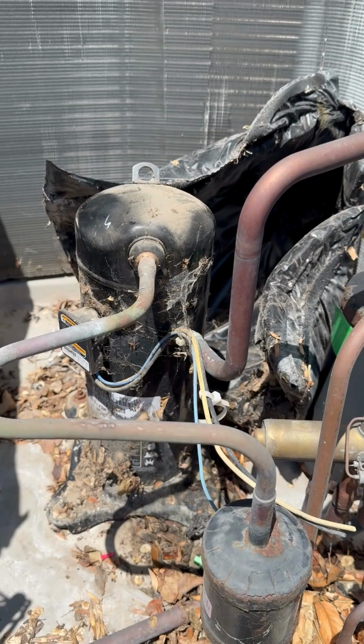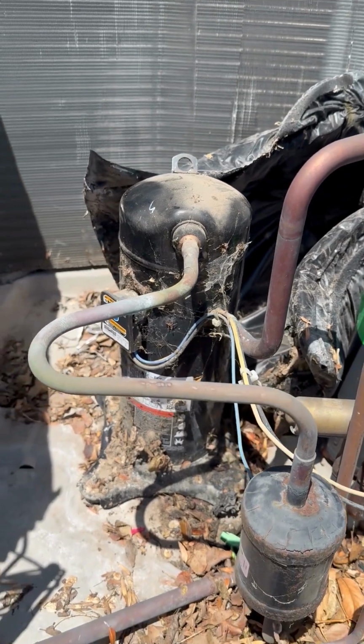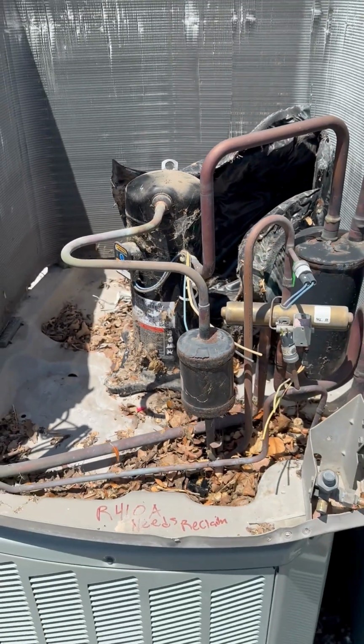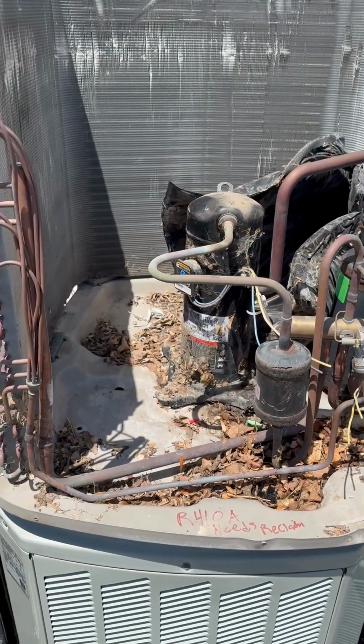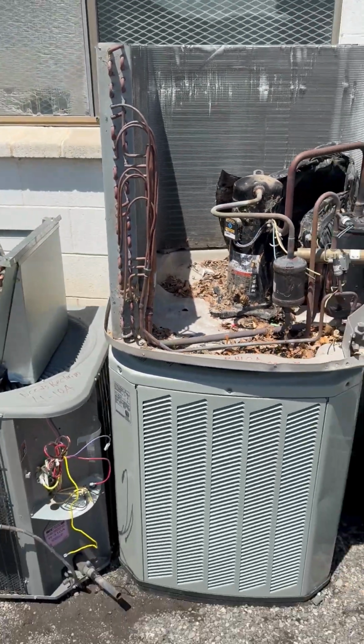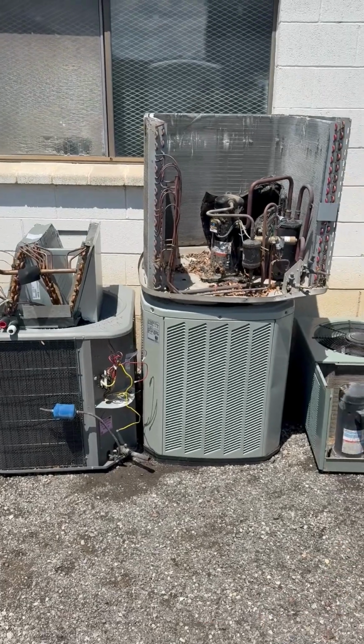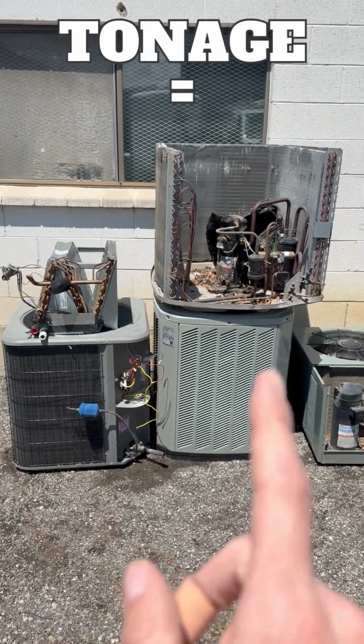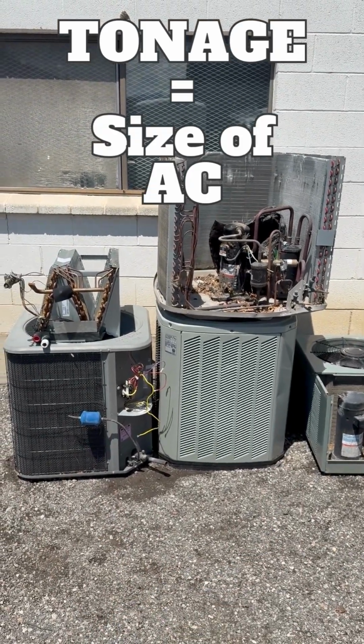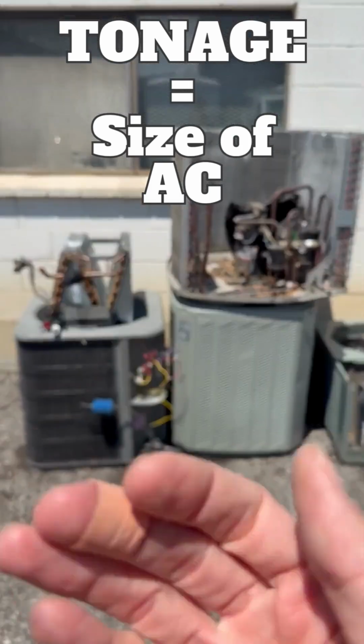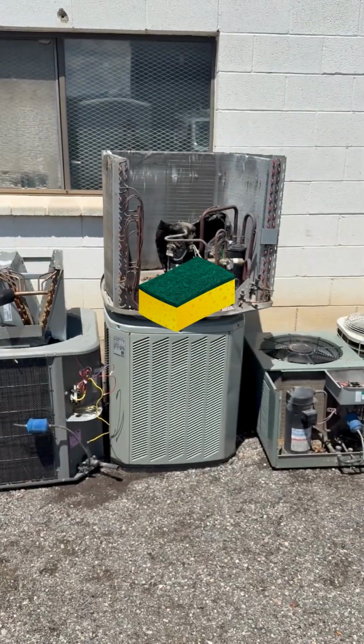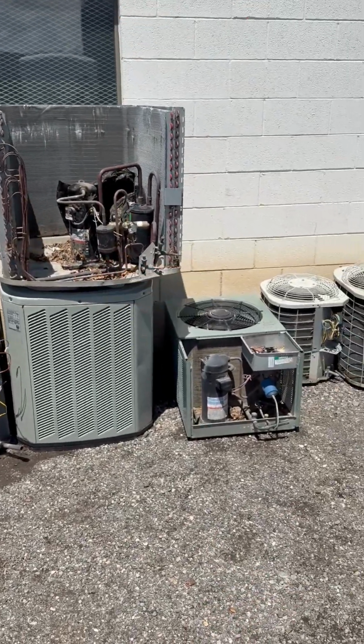And once it happens, our compressor once again compresses and allows that high pressure, high temperature vapor to go through the condenser coil. What's really interesting about this process is that the tonnage of the AC that you have is referring to the amount of heat that this system is going to absorb inside, transfer to the outdoor unit, and reject into the atmosphere.